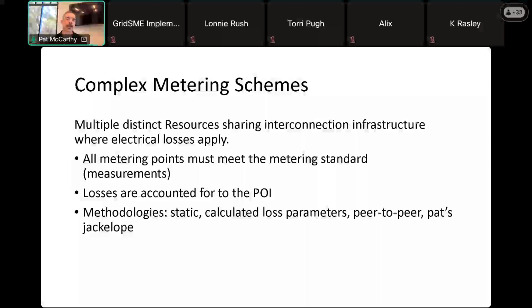So you have a long transmission line between you and the grid. That's going to consume energy. Those losses need to be subtracted from the energy that you're measuring way back at your 35 kV bus. Likewise, there's a transformer that's also going to consume power. Those losses need to be subtracted from wherever your point of measurement is, if it's between that and the point of sale.